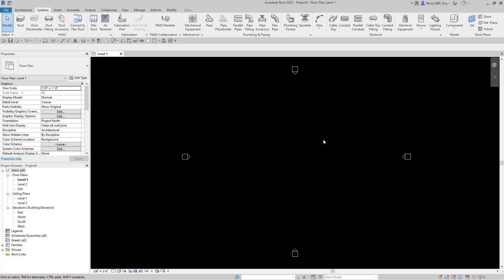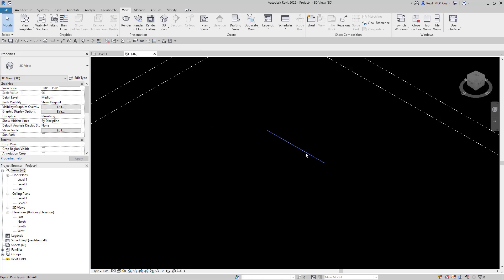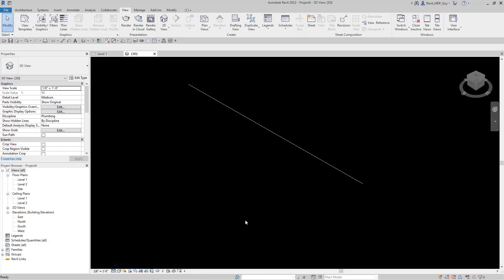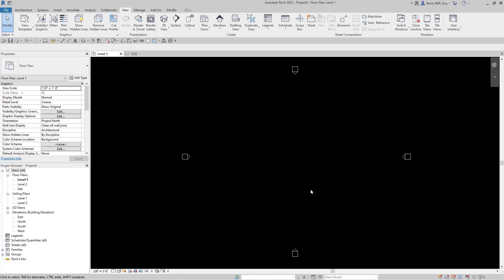There is pipe being drawn in the project, and the way we can check that is if we go to View and click on a default 3D view, you'll see that Revit did draw this piece of pipe — we just can't see it in our view, and there can be a couple of reasons for that. The first thing we need to check is the view range. Under your Properties, if you go to View Range and hit Edit, you'll see that there is a bottom at zero at Level 1, and there's also a top at seven foot six.